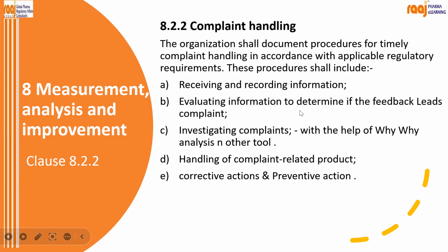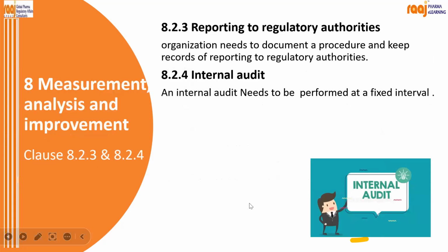Then how you evaluate the information to determine if the feedback leads to a complaint. Investigating that complaint with the help of why-why analysis or any other tool. Then handling of complaint-related products, and corrective action, preventive action. This is the normal procedure we have to write down for complaint handling. You have to document that procedure about complaint handling. Then 8.2.3 talks about reporting to regulatory authorities.